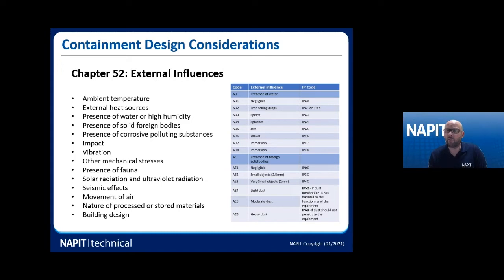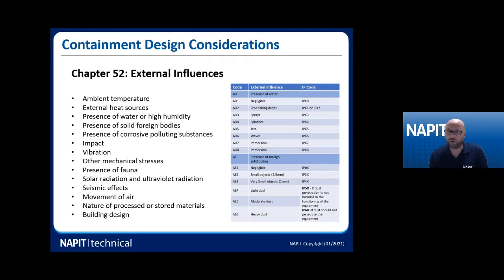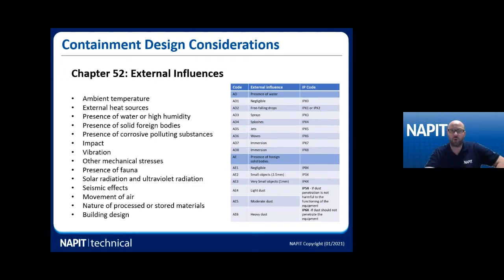Here's an example of IP codes. For presence of water, the classification is 'AD' followed by a number from one to eight, where one is negligible through to eight for immersion. On the right hand side we have the International Protection code which relates to protection against those areas. If it's got an 'X' and then a number, that's generally when we're dealing with water. Where we're dealing with solid objects it's a number then 'X' on the end. For example, IP44 would indicate protection against small objects and water splashes.